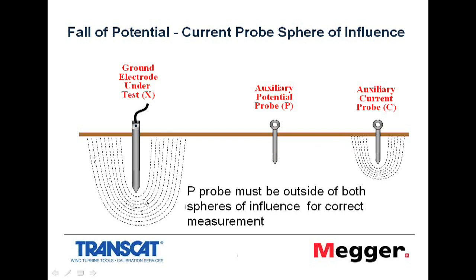Just to quickly describe what that means, if you can imagine the earth mass around the electrode as a series of shells. Let's imagine the shells are all of equal thickness, and as you can imagine, as I move away from my electrode, the volume of earth in each shell is getting bigger and bigger, and therefore the amount of additional resistance being added as I move away from the electrode is becoming less and less. Once you get to the point where the amount of additional resistance is 0 or negligible, that's the point where we would say we're outside the sphere of influence.